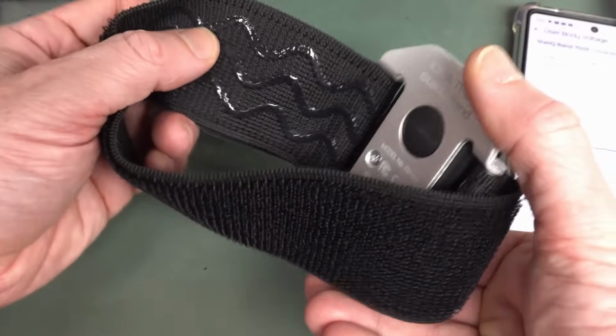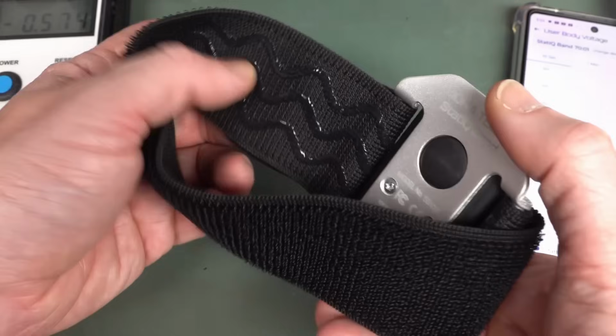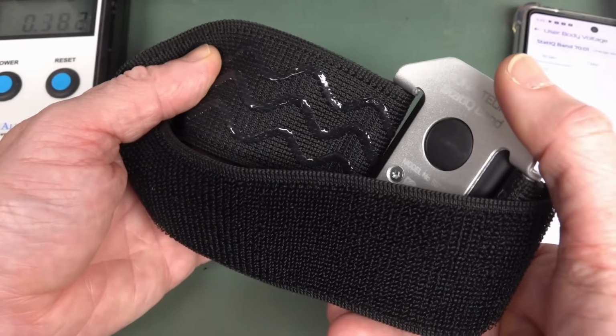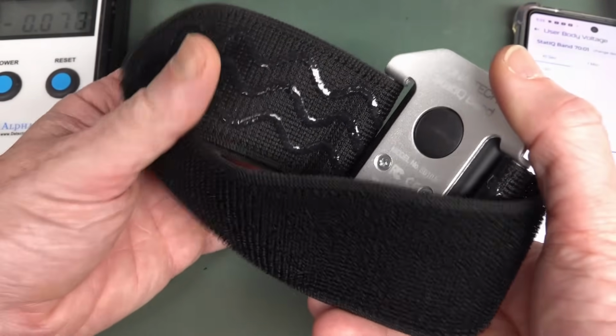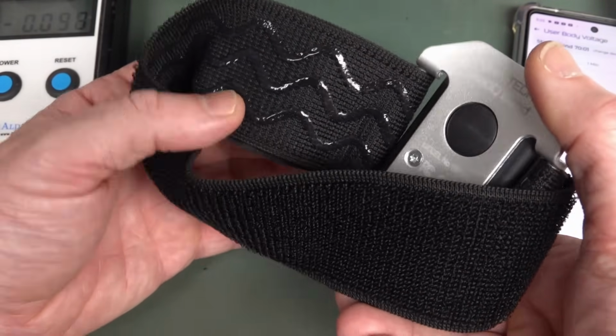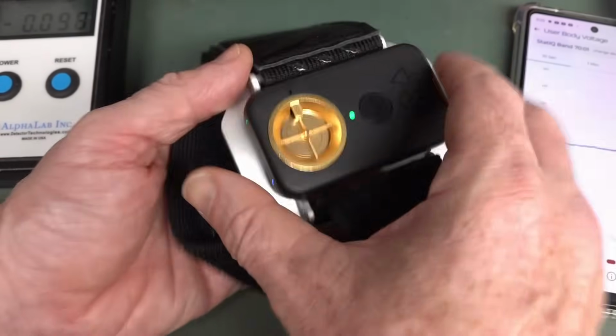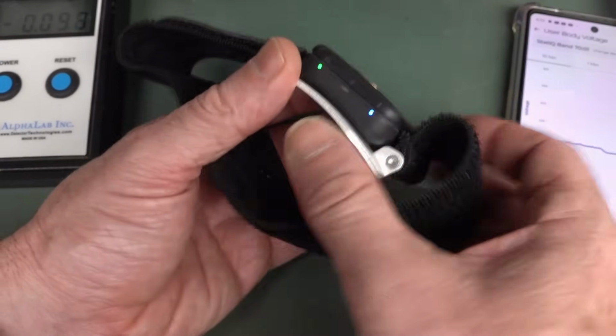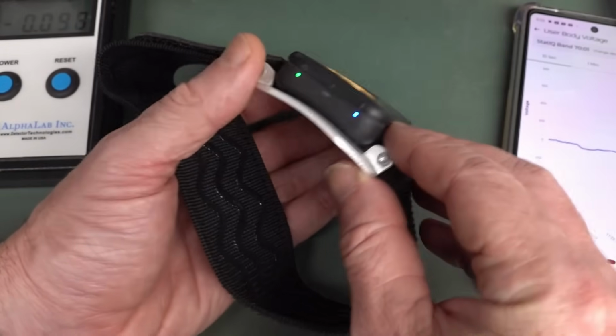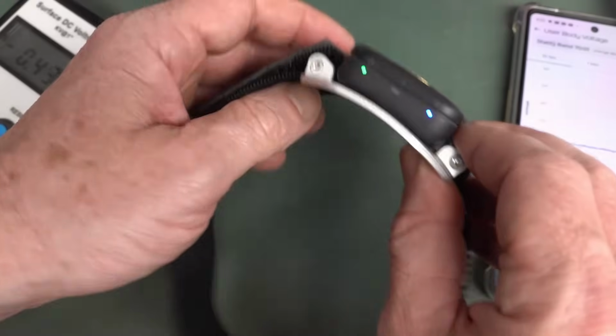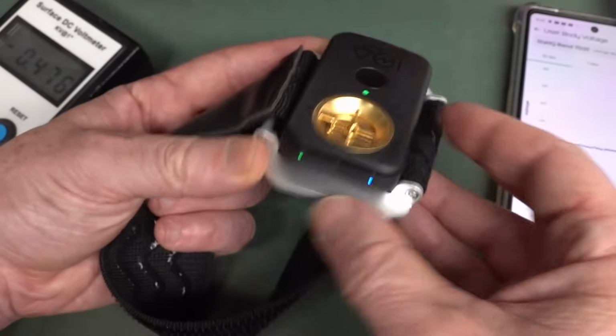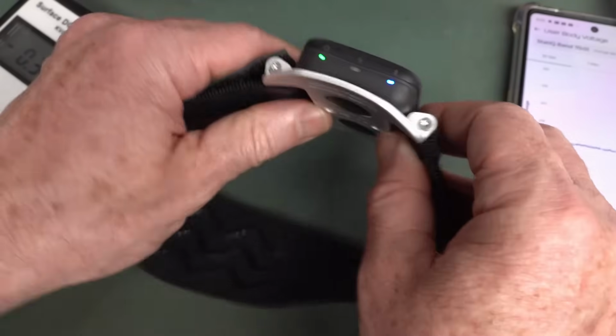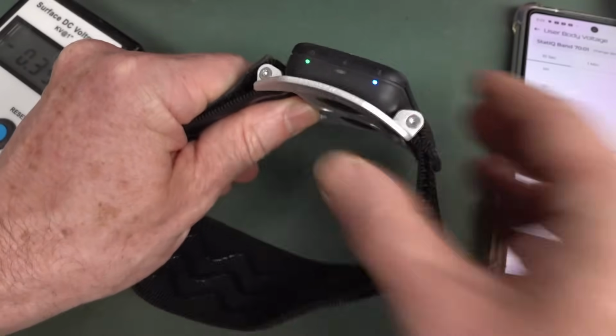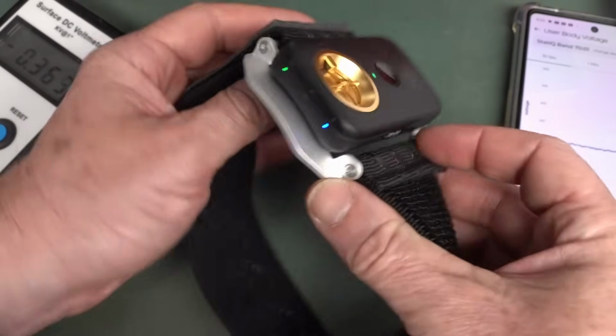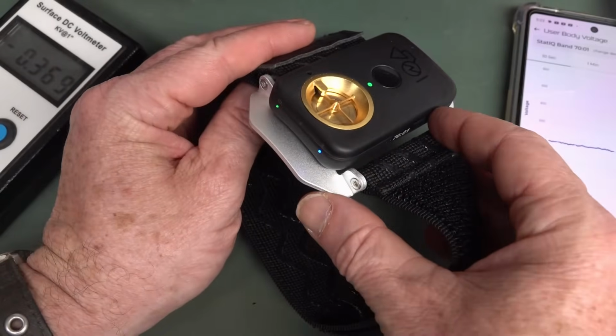And that also explains why that dodgy ESD coat, which obviously is crap now, didn't work, because it was basically an insulator, and you've got an insulator between there and the spinning detection plate on the top, or the spinning detection mechanism on the top, because it's not just that one plate. So that just upset all of the readings. So that's why it didn't work. But when I put on a real working ESD coat, or I used the shirt that they provided, a proper conductive coat, then it's actually measuring the surface of my body.